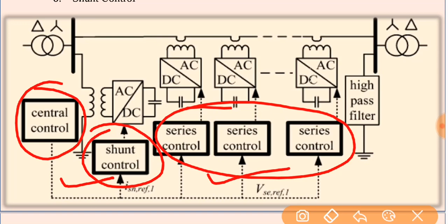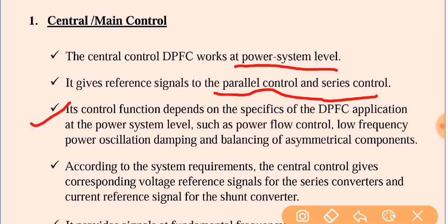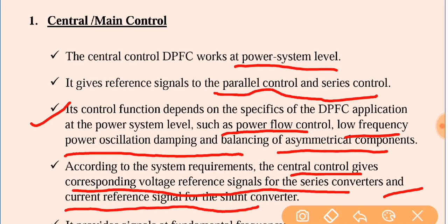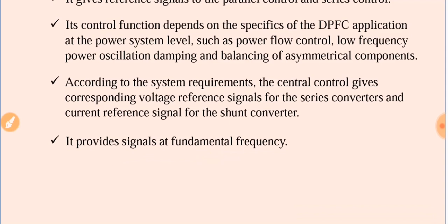First, central control or main control. The central control of the DPFC works at the power system level. It gives reference signals to the parallel control and series control. Its control function depends on the specifics of the DPFC application at the power system level, such as power flow control, low frequency power oscillation damping, and balancing of asymmetrical components. According to the system requirement, the central control gives the corresponding voltage reference signal for the series converter and current reference signal for the shunt converters. Central control provides these signals at the fundamental frequency. This is the work of central control.